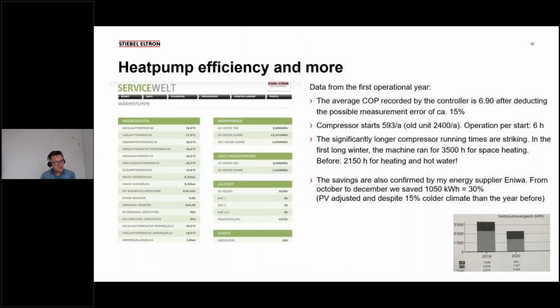Some results: after 1 year of operation, I found out that the COP of this installation for heating is around 6.9, after already deducting some measuring errors. What's really interesting is that because it's an inverter machine, it runs a lot longer than an on-off machine. So it's 3,500 hours compared to 2,150 hours. That's a lot more.